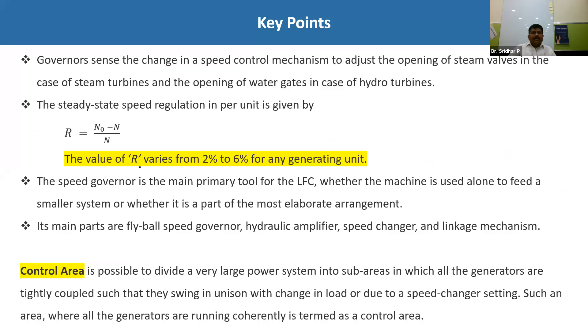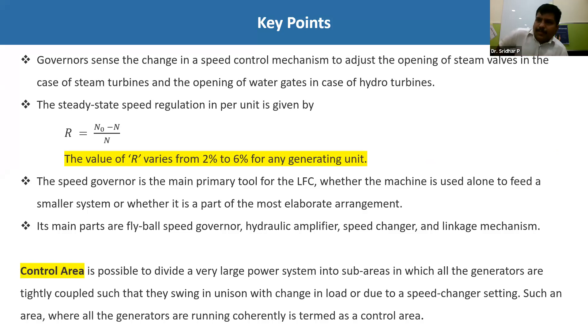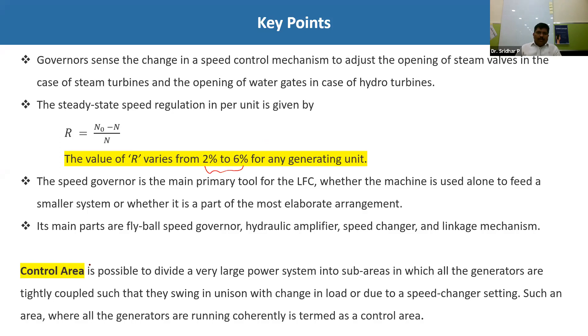Steady-state speed regulation R is defined as (no-load speed − full-load speed) / full-load speed. Under no dynamic load changes, the speed is n₀; with dynamic load changes, speed changes and is denoted n_r. The value of R typically varies from 2% to 6% for any generating unit.